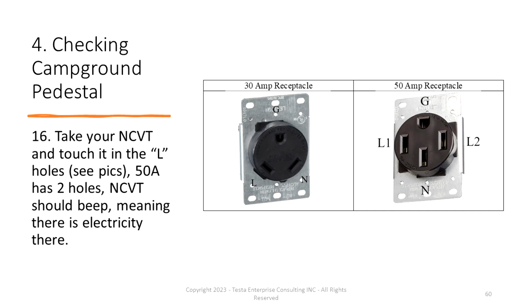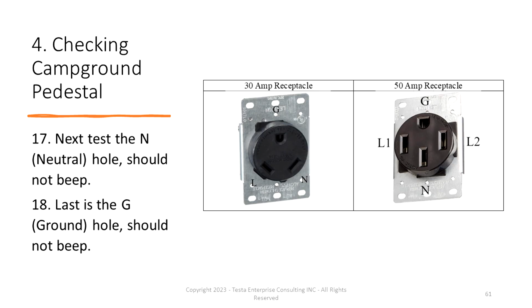You should see electricity on L1, L2 for 50 amp, and L for 30 amp, with the breaker on. Next, you're going to test the N, the neutral hole. For the 30 amp, it's off to the lower right; for the 50 amp, it's the one on the bottom. Last, you're going to want to check the ground hole, the G, which is the top half-moon-like shape. On the 30 amp it's at the top, and it's the same on the 50 amp.